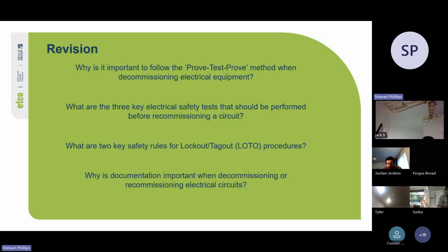When we do lockout tagout here in the workshop with the pre-trade students, they'll get 230 volts, but as soon as they flick the circuit breaker off, they'll still be getting about 4 volts until I turn an actual isolator at the start before the main switch, and then there's zero. Sometimes, because other machines are running, it will induce a small voltage.